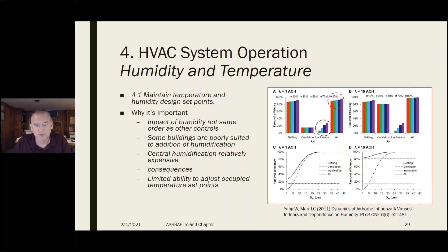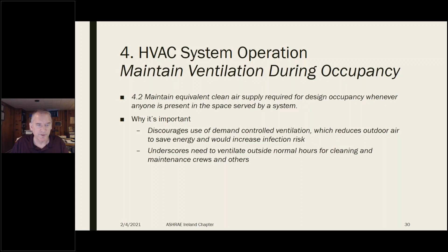Another thing that's been covered in the recommendations is maintaining ventilation during occupancy. We don't need to maintain ventilation 24/7, but we should have the designed ventilation whenever there are people in a space, including janitorial personnel and maintenance staff after normal business hours. This recommendation discourages the use of demand-controlled ventilation to reduce ventilation below that design occupancy amount, because that will save some energy, but will also significantly increase risk. And again, it underscores the need to ventilate whenever there are people present.